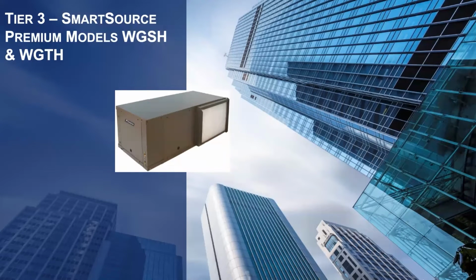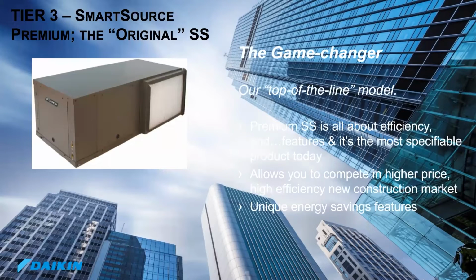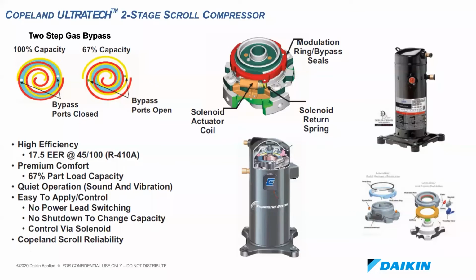The Smart Source premium models are our top of the line and most efficient models. It includes the most features of any other manufacturer. We offer a lot of options on this product. Here we have an illustration of the 2-stage scroll compressor. It's the bypass port that you see on the upper left, built into the scroll set, that is either open or closed, which allows for part or full load operation.